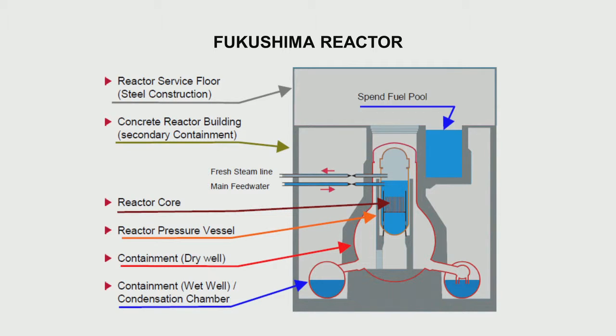Now let us go to the Fukushima reactor. Fukushima reactor is a boiling water reactor — it is a pressure vessel boiling water reactor, unlike the Chernobyl reactor. All the core elements are there, steam is produced, and it goes to the turbine. At the top they have a spent fuel pool where fuel that has seen enough burn-up in the core is kept in a tank full of water with continuous cooling so that its temperature is kept low. There are different containments: the reactor pressure vessel, the dry well, the wet well, and of course the concrete building.